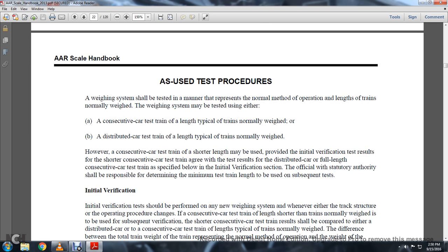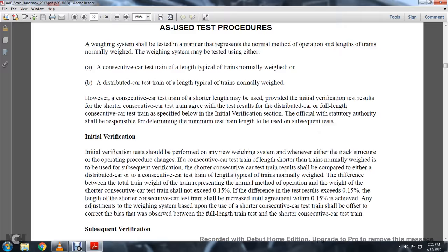As-used test procedure: a weighing system shall be tested in the manner representing the normal method of operation and length of trains normally weighed. The weighing system may be tested using either a consecutive car testing train typical of the train normally weighed, or a distributed car testing train typical of the normal trains weighed. However, a shorter consecutive car testing train may be used provided initial verification testing results show the shorter consecutive car train agrees with test results distributed with the car full length of the consecutive car train specified. With the initial verification, the official statutory authority shall be responsible for determining the minimum testing train length to be used in subsequent tests.